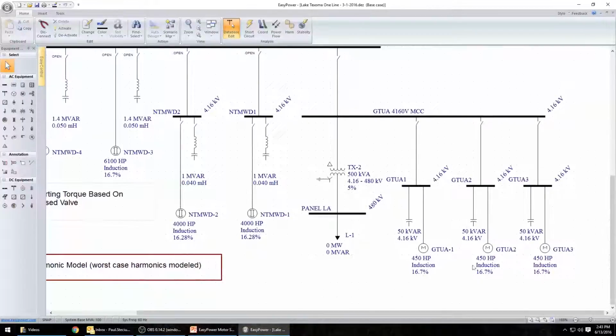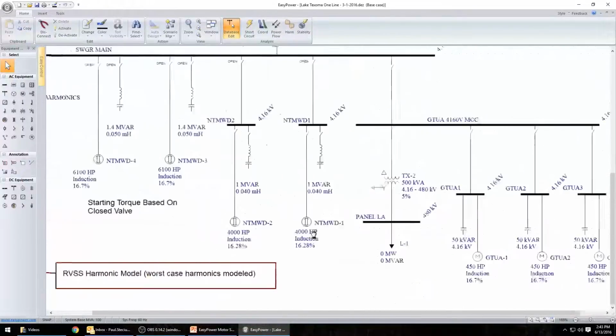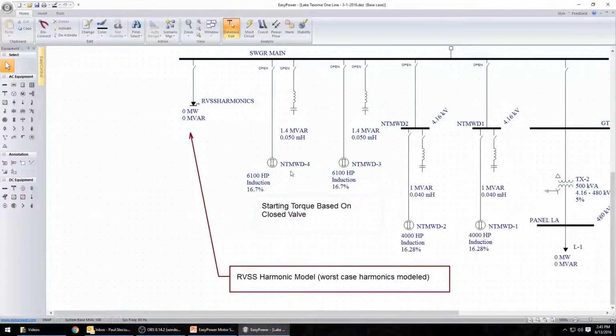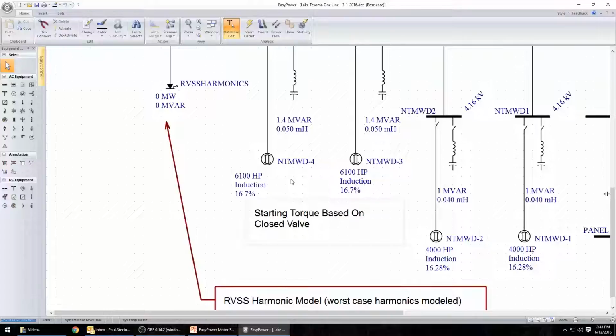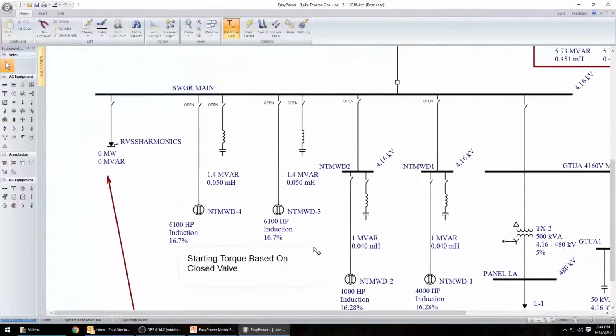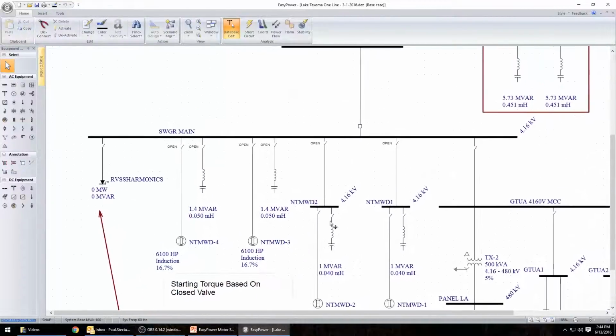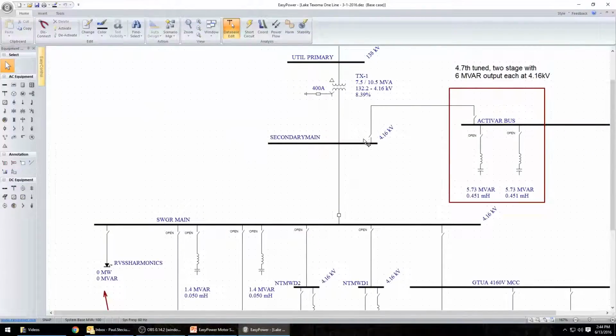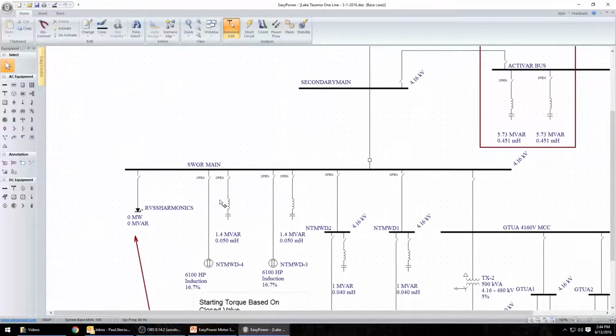These motors over here we have not modeled in the dynamic analysis package, and then also the 6,100 horsepower motors we have modeled in the dynamic analysis package. So what was going on is they purchased two 6,100 horsepower motors here. They equipped it with soft starts, and the customer was given constraints by the local utility as to what to maintain the primary and secondary voltages at, actually the primary voltage only, and the soft starts were installed for the purpose of limiting the voltage sag and inrush current to the utility's limits.